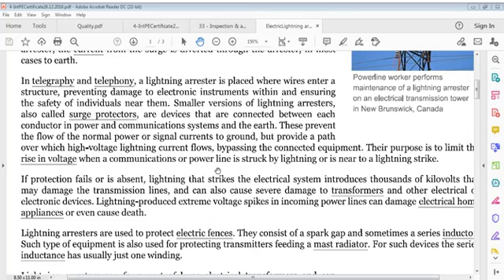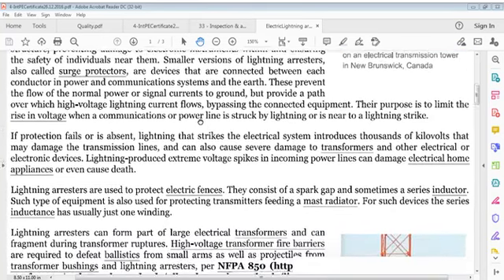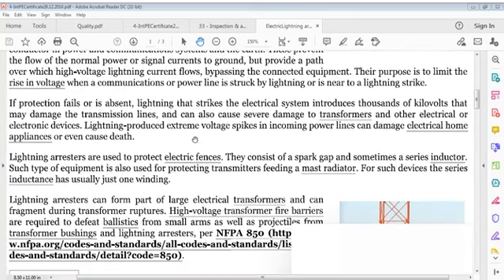These prevent the flow of normal power or signal currents to ground, but provide a path over which high voltage lightning current flows, bypassing connected equipment. The purpose is to limit the rise in voltage when a communication or power line is struck by lightning or is near to a lightning strike.